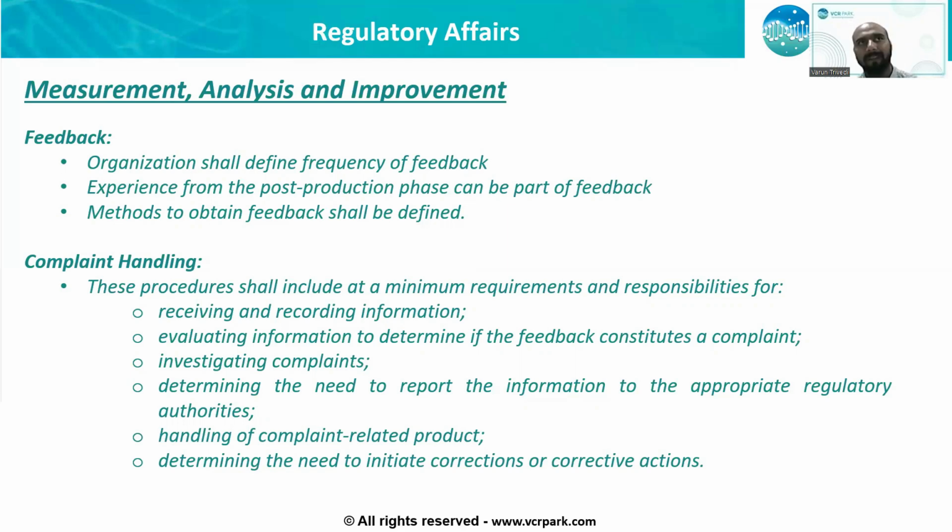Complaints are basically when the product fails to meet certain requirements. If you have defined that the product will capture ECG, and it is not able to capture the ECG of the patient, then it has failed to meet the requirement, and that constitutes a complaint. It is very important for us to log these complaints, investigate them, and understand the nature of the complaints. If the complaints are due to any adverse event, then the same shall be reported to the regulatory authorities. Necessary actions that we need to take to close a complaint shall be documented appropriately. If a particular complaint is not to be investigated, then the justification for the same shall be recorded and documented.